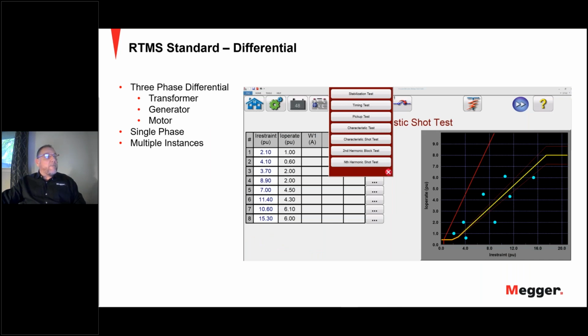Okay, moving on to differential. The differential test provides a quick and easy approach to testing three-phase transformer, motor, generator, and single-phase transformer differential relays. In the settings screen of the differential test, the user can select the transformer primary and secondary winding configurations, enter the primary and secondary voltage ratings, CT ratios, transformer MVA rating, single-phase pickup factor, and much more, as well as relay specific settings.